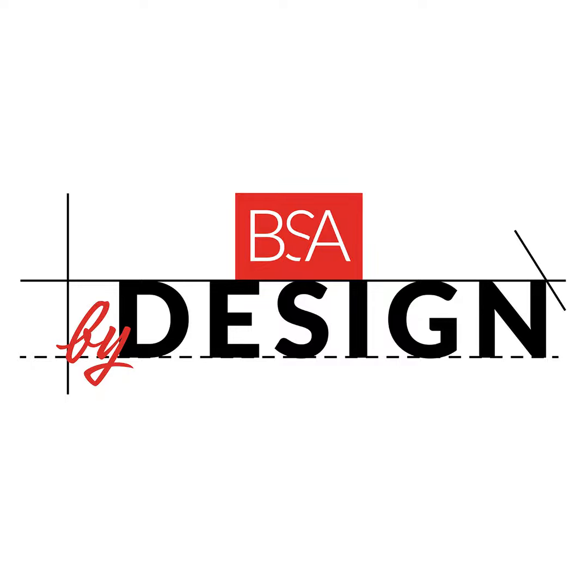Yeah, I think users see differently. Seeing something on a drawing is very different than seeing it in person. We've been in mock-ups where the gas placements on a head wall are actually Velcro or stuck on. Where that stuff ends up has a big effect on clinical workflow. It's not thought of as medical equipment, but it is, because of where this stuff sits. They're able to actually pick up a piece, move a gas from here to here, and talk through those types of things, or move the cart from this side to this side, or move a computer a little further away, or say, I don't like this table that we're going to buy, it doesn't allow enough flexibility. So them being able to see that stuff, visualization is a big deal, and actually use what's planned on being purchased. And the moving of the gases, sometimes it can get infuriating when you're standing in the room and they say, we just need to nudge this over like an inch. And you're like, well, what does an inch mean?